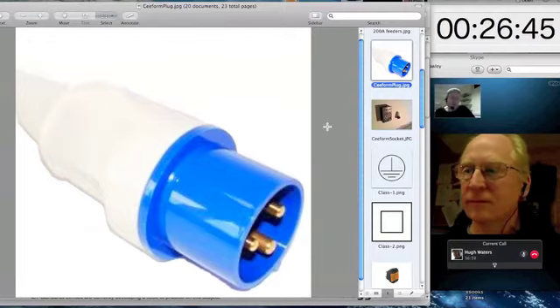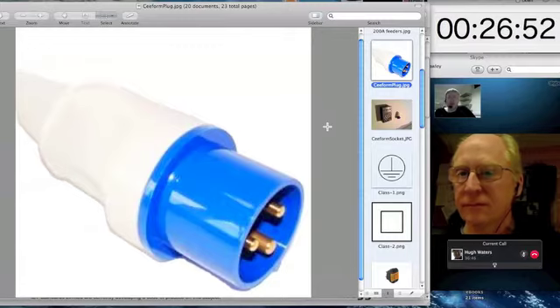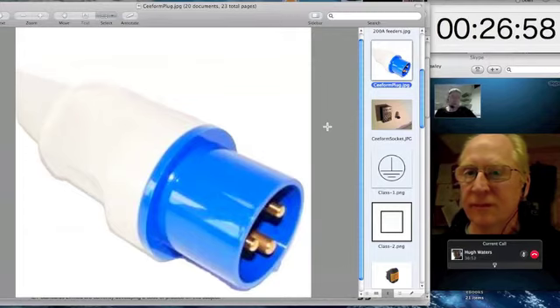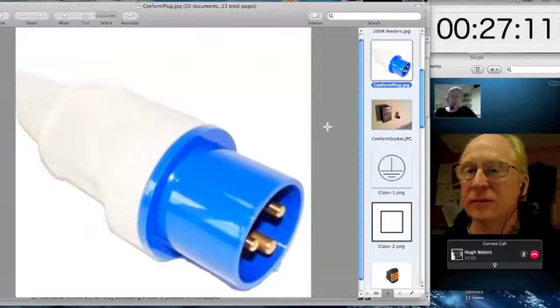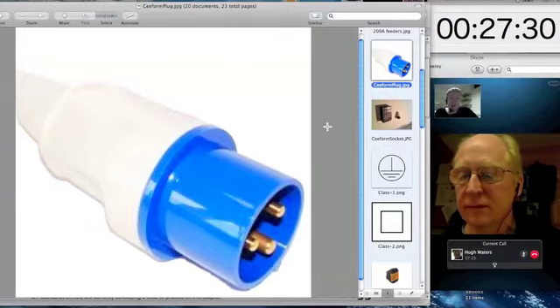And in fact, all the class 1 mains that we deal with has a safety earth, which comes back to the earth bus bar at the mains intake of your facility, and if you know where the mains intake is, you could pop down. It might be in the same room as the lines room. That's often the case, and you can see where all this is derived from. But nowadays that earth is provided by the electricity company, and in fact it goes back to the neutral point at the step down transformer at the substation at the end of your street, or 2 or 3 streets away. And that's a good thick quality bit of copper coming all the way to your street to provide that safety earth. But in the States, having an earth that's derived from a piece of copper buried in the ground outside is still common.